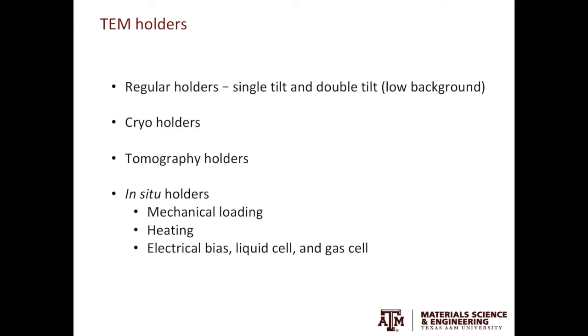We have the regular holders for most applications. We also have the cryo holders for imaging beam sensitive materials such as biological specimens and lithium containing materials. The tomography holders which reconstruct the 2D projections back into 3D objects, and also the in-situ holders. For the in-situ holders you can apply mechanical load, you can do heating or cooling as well as electrical bias, liquid and gas.